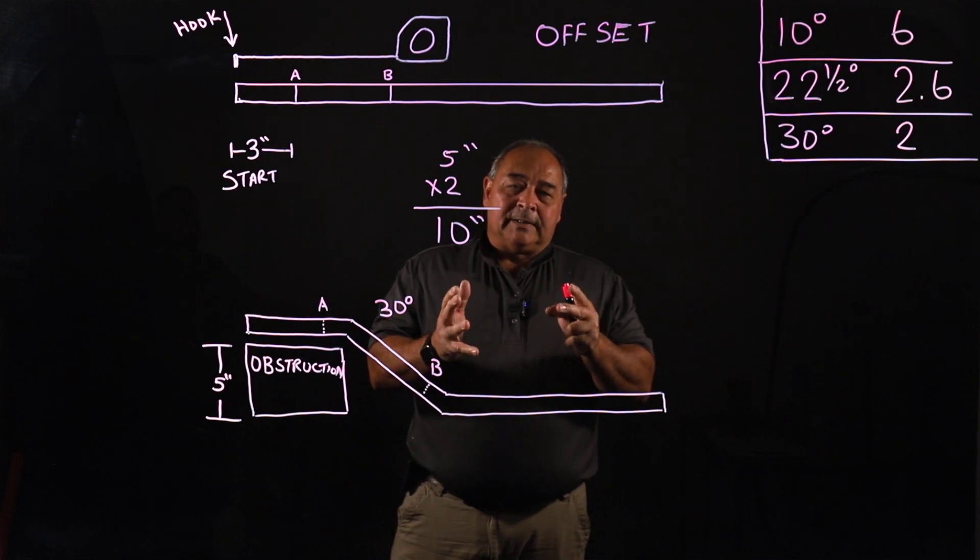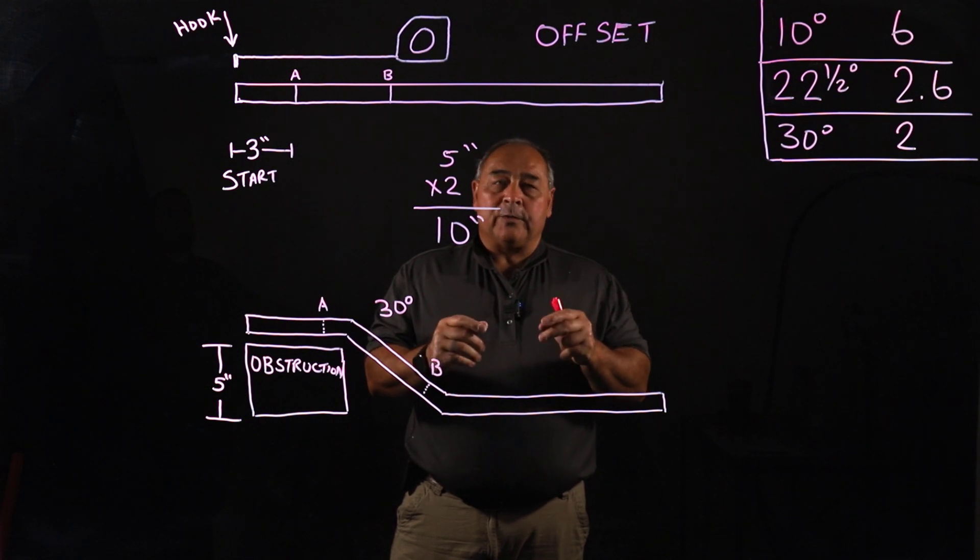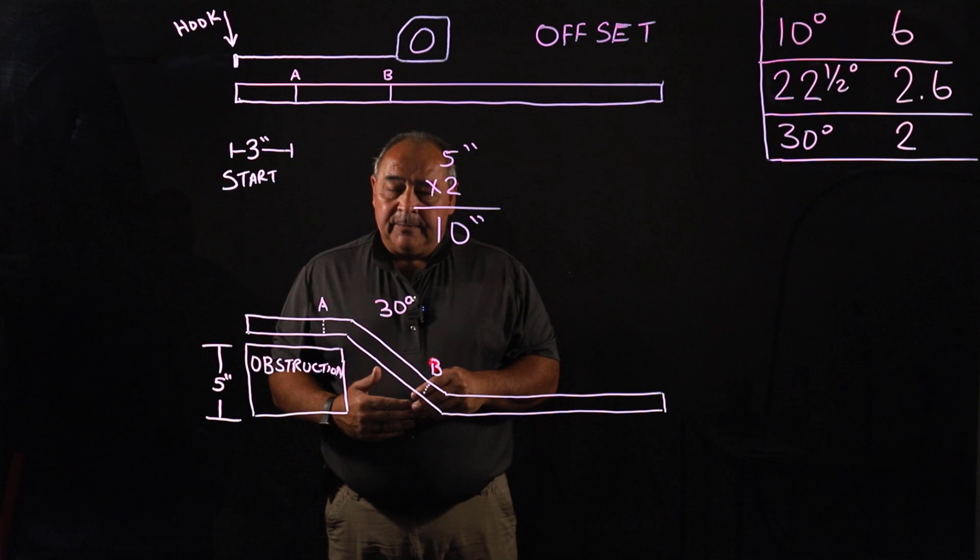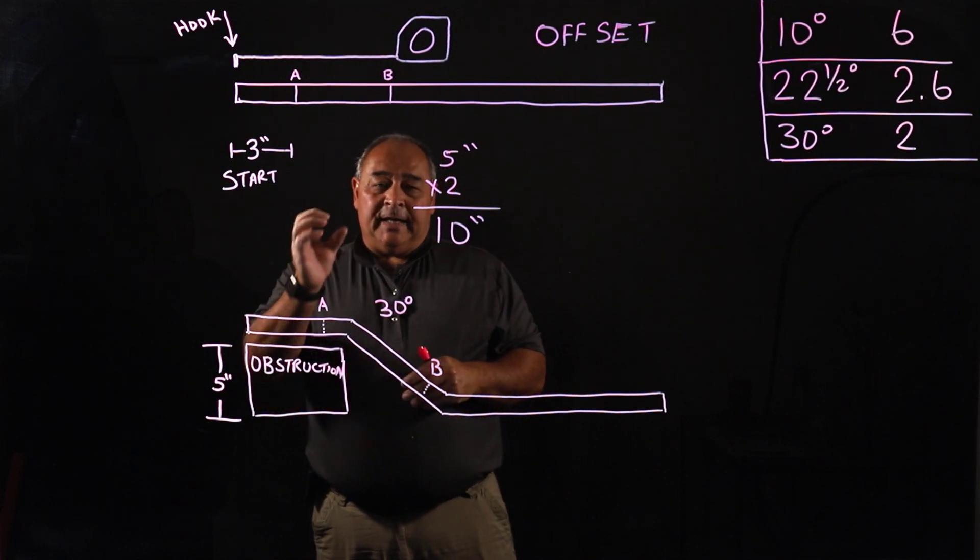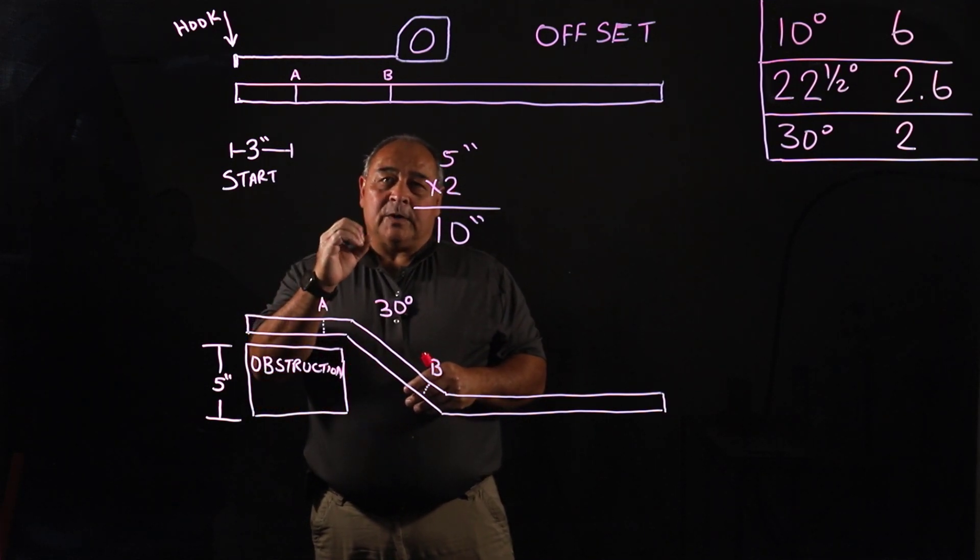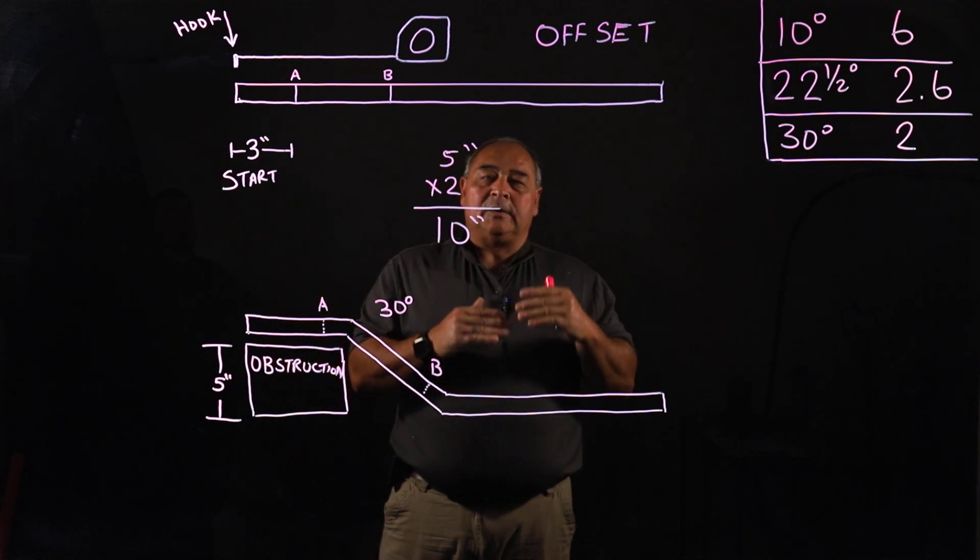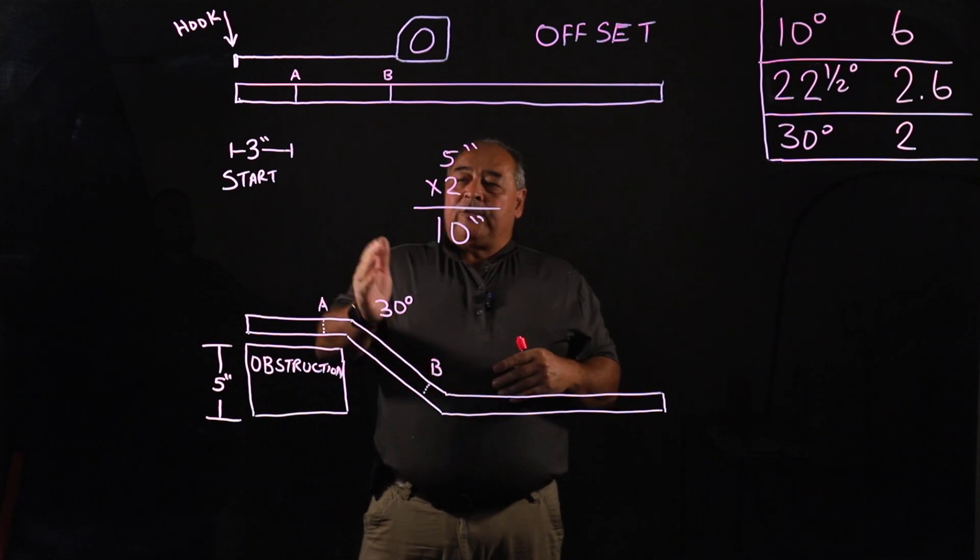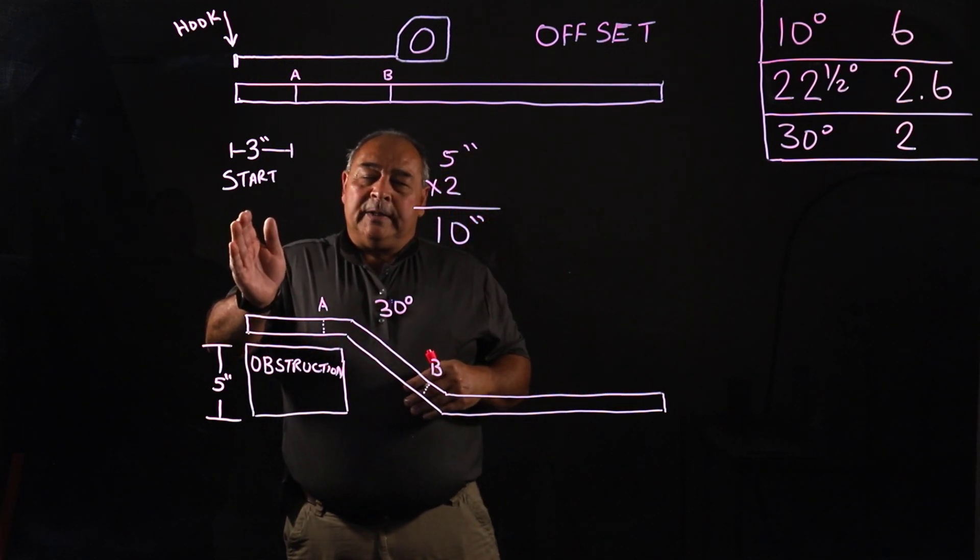And that's about a little bit more than an inch and three quarters for a three quarter inch. And if we're real close to that end, we can actually egg shape that circular conduit and make it not circular anymore, kind of make it look like an egg at the end because we're too close to the end. Three inches is a safe start point that I suggest.